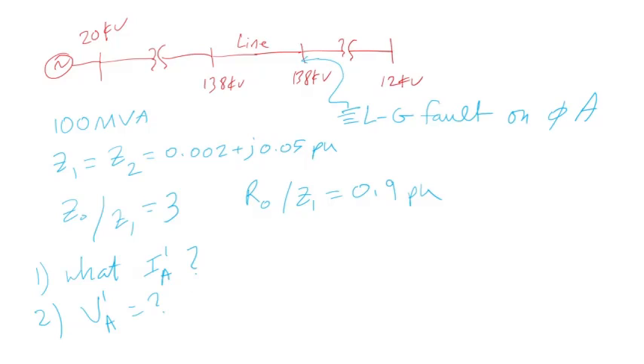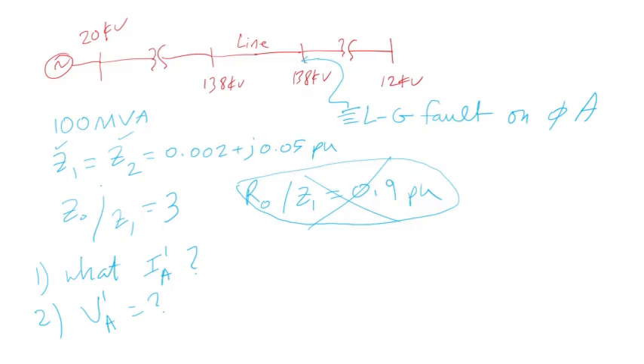Looking at this system, you might be given some information that is really just a distraction. For instance, the zero sequence resistance ratio — you would need that if you are calculating the effective grounding ratio, but for calculating the fault current, you need the positive sequence impedance, which is given, and the zero sequence impedance, which is given as a ratio, so you can calculate that. The pre-fault voltage is 1.05 per unit. That's all you need to calculate the fault current.